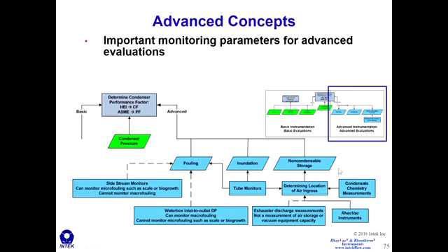Now, yesterday we discussed the left side of this tree for basic performance analysis. Today we're going to discuss the right side of the tree. These 3 condenser performance degradation mechanisms that I just talked about are the focus for this advanced analysis. So they're shown here: fouling and non-condensable storage. Inundation is another one that I'll mention.